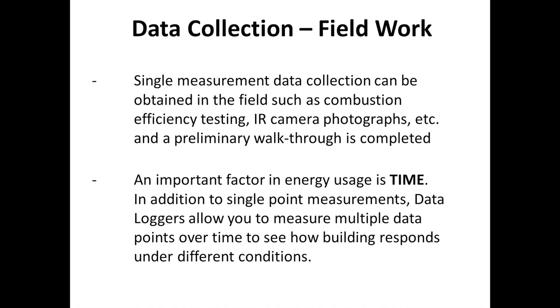But an important factor to consider with energy usage is time. Data loggers allow us to log different conditions and parameters over time in the building, things like temperature and relative humidity. We can look at event changes such as lights on or off. We can look at light sensitivity, how many lumens per square foot were produced by a lighting fixture in a certain area, and also look at other factors we might not be able to see if we just happen to go into a building on any given day.